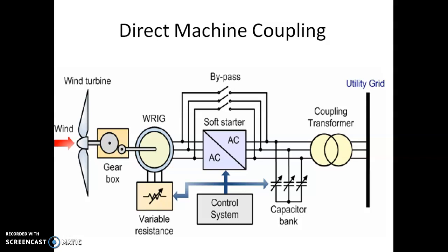For constant mechanical power resulting in constant rotational shaft speed, synchronous machines are preferable. Whereas if there is strong variation in power, we use an induction machine. If slow rotation speed turbines are there, we use a permanent magnet synchronous machine. Then a linear synchronous machine is used to convert vibration energy into electrical energy.